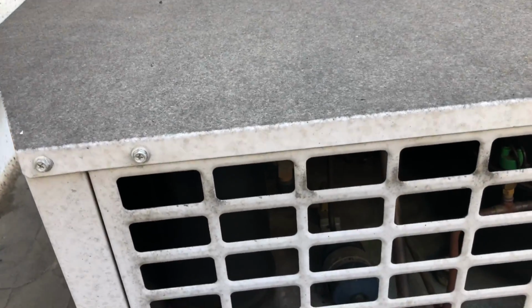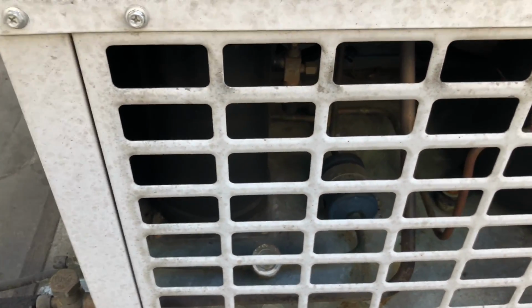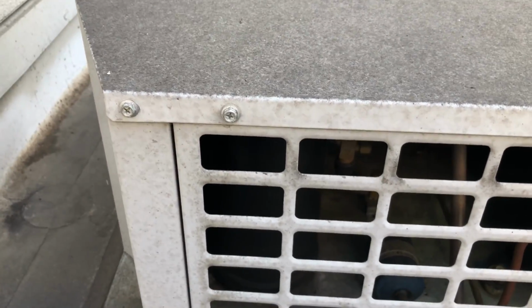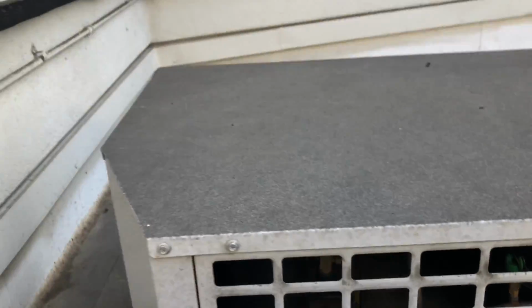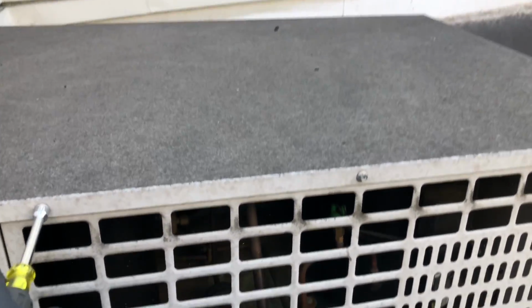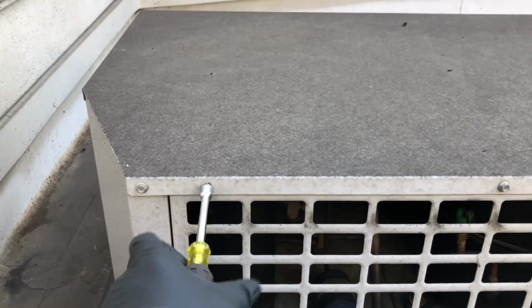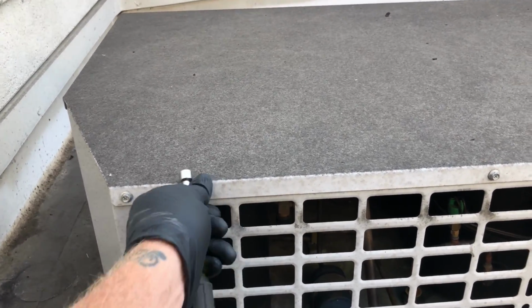Okay, so I'm here taking the panel off, and I can smell that heat smell, like when the condenser's overheated. So I'm wondering if this thing might have failed condenser fan motors. You guys know the smell I'm talking about. Maybe this thing cycled off on high head pressure.